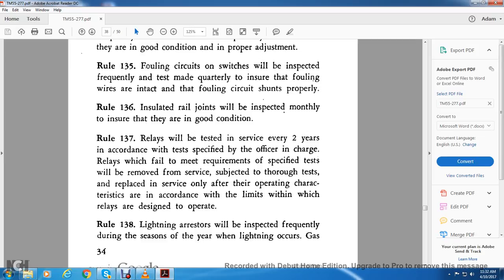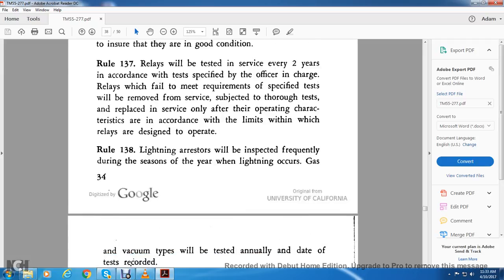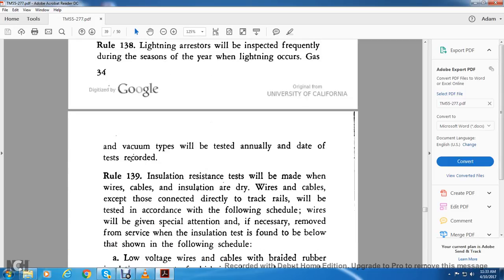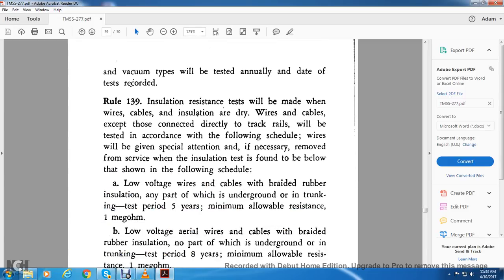Rule 137. Relays will be tested and inspected every 2 years in accordance with the specified test. Relays that fail to meet the requirements of the specified test will be removed from service, subjected to the test, and replaced in service only after the operating characteristics are in accordance with the limits within which the relays are designed to operate. Rule 138. Lightning arresters will be inspected frequently during the season of the year when lightning occurs. Gas and vacuum types will be tested annually and the date of the test recorded.